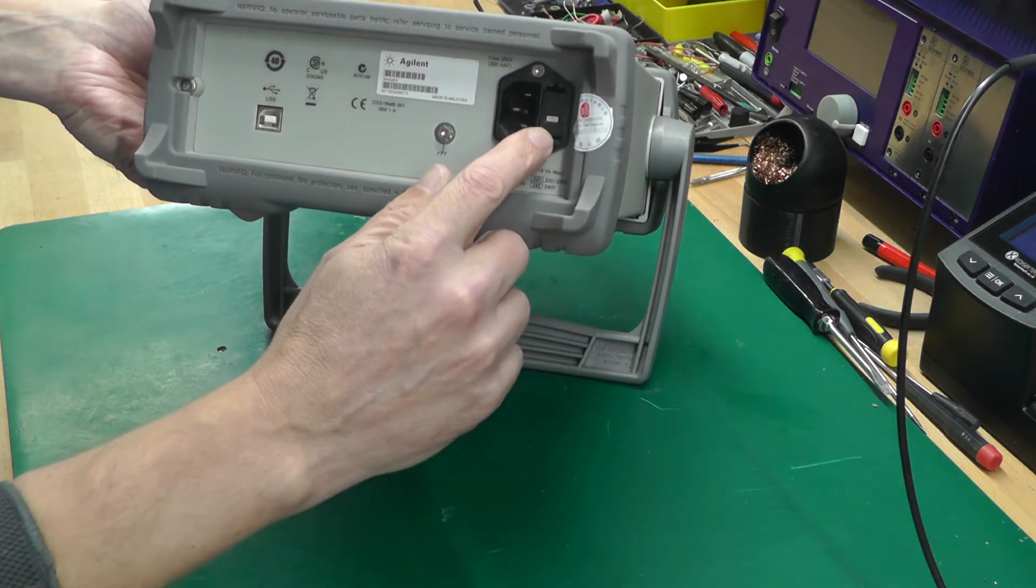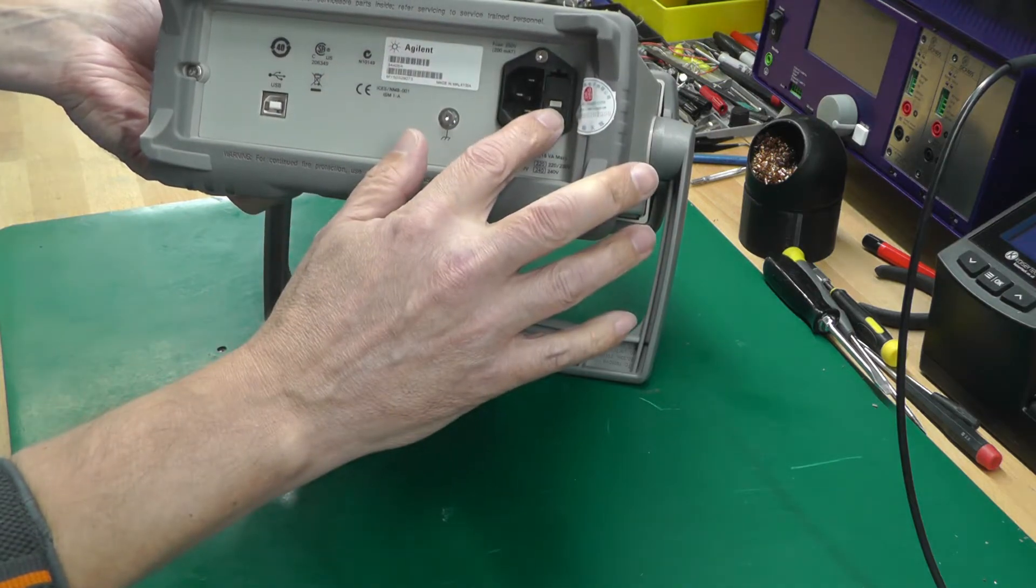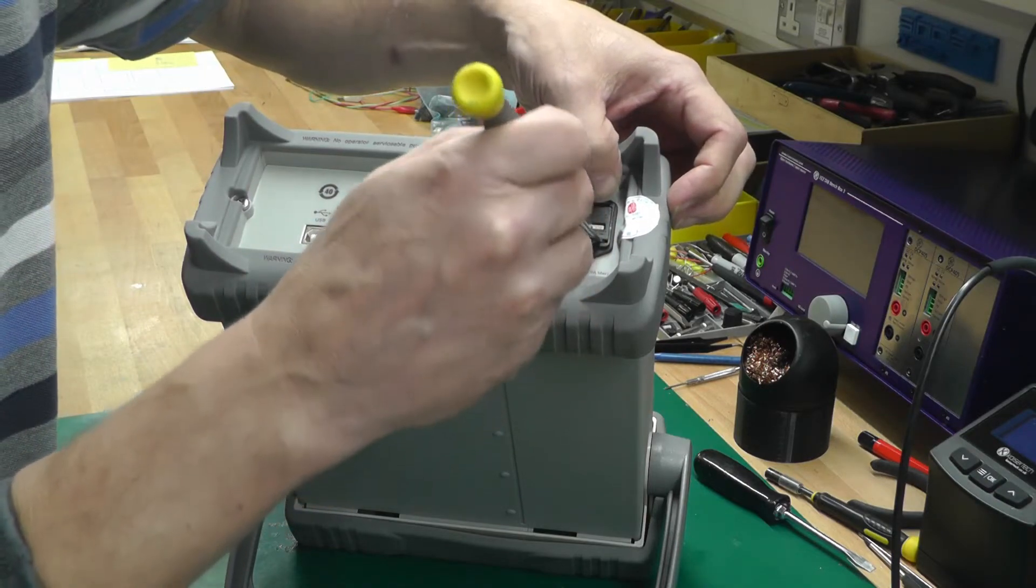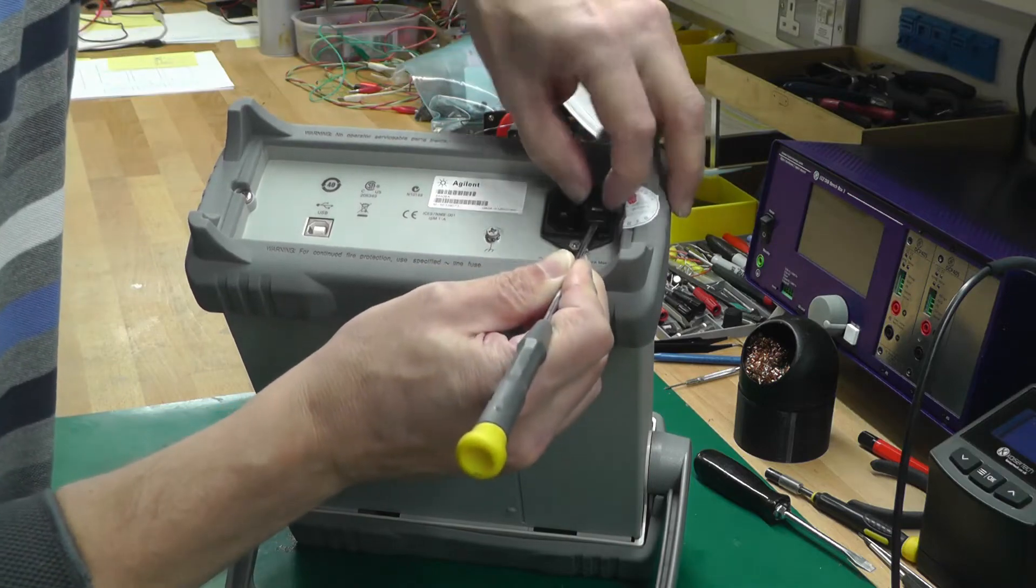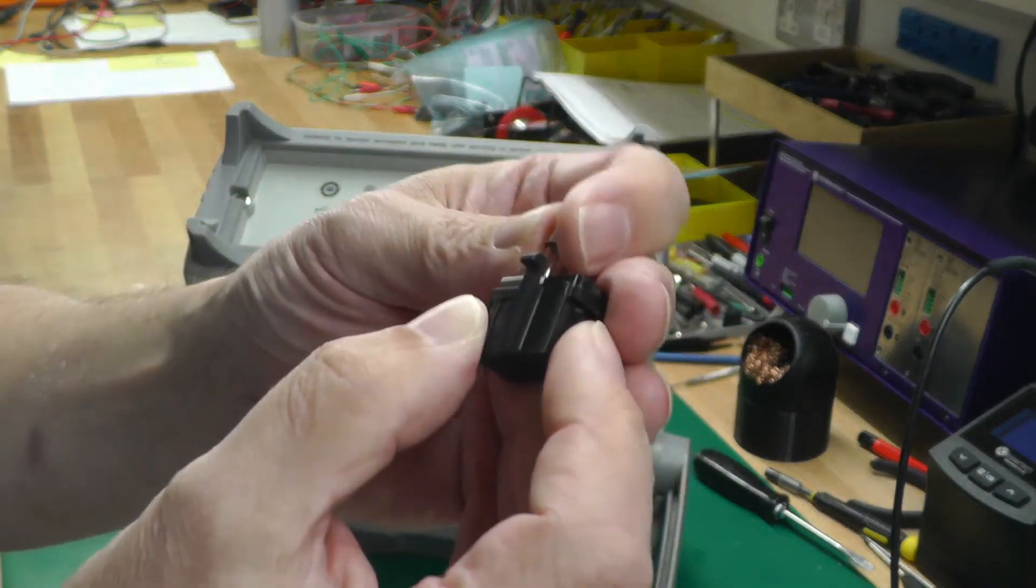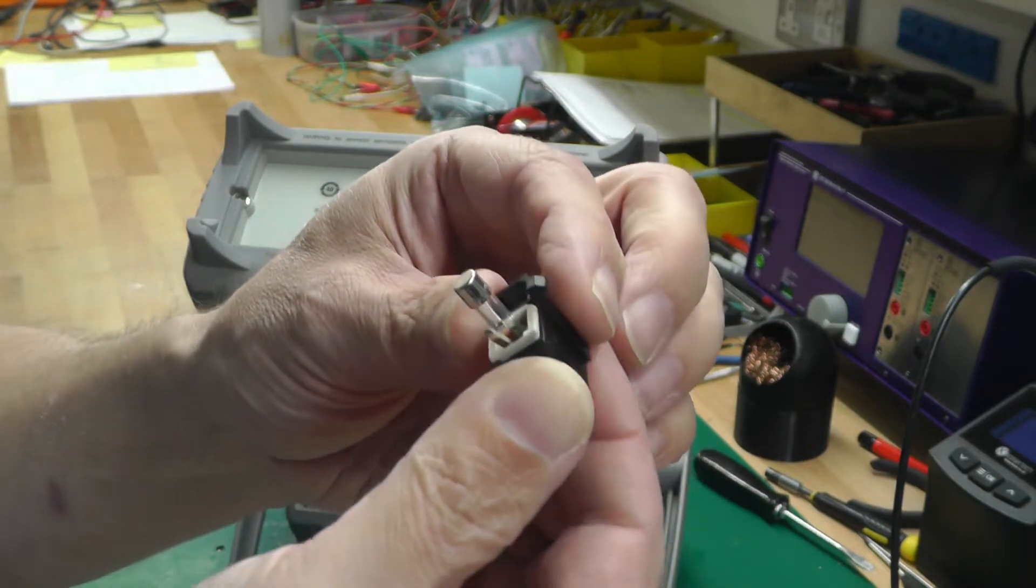It's currently set for 220 volts, so let's take that out, then turn it around and get it set for 240 volts before I do anything. Okay, there we go. I'll have a quick look at the fuse whilst we're in here - the fuse looks to be intact. The way these line selectors work is you just pull out the gray part here.